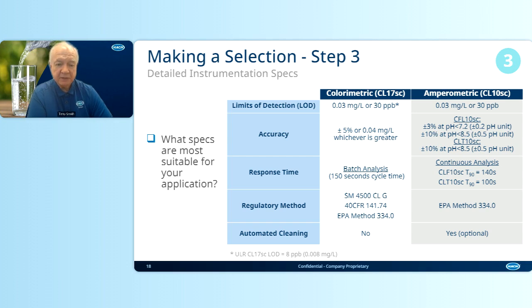Response time, the batch process is a 150 second cycle time. Continuous analysis for the CLF10, but we do not get a full response. T90, 90% of the total response, takes 140 seconds. Whereas the CLT10, 90% of the total response takes 100 seconds. So there's really not a great deal of difference between those. On regulatory method, the standard method 4500-Cl G, the 40 CFR 141.74, or the EPA method 334 are usable on the colorimetric method. On amperometric, EPA method 334.0 is the only method.